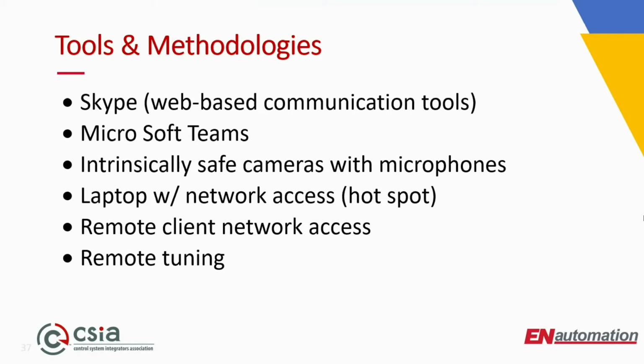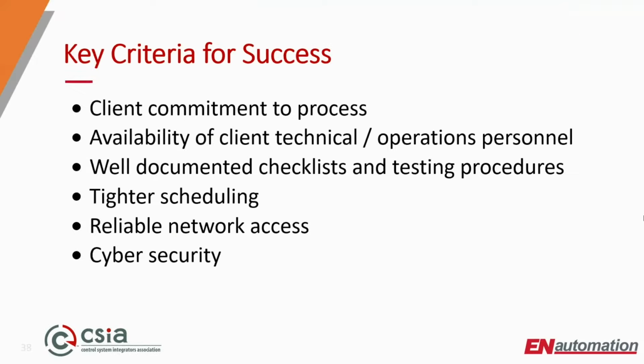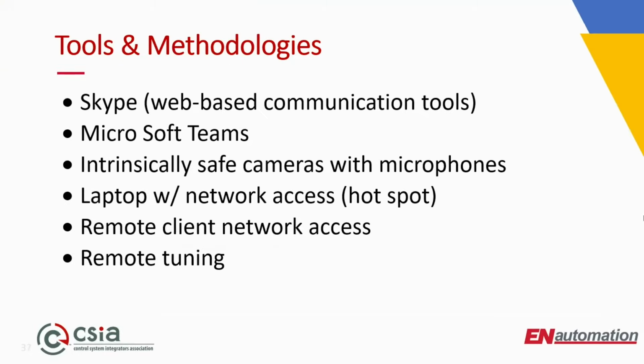One of the things we do on site is tuning, and that was a bit of a challenge. The software packages we use usually require direct access to the PLC in the system - it extracts data, comes up with tuning parameters, and we download it to tune the system. To do it remotely, we had to develop software to extract that information over the network, load it into our tuning software in the office, come up with the parameters, and then download that to the system.